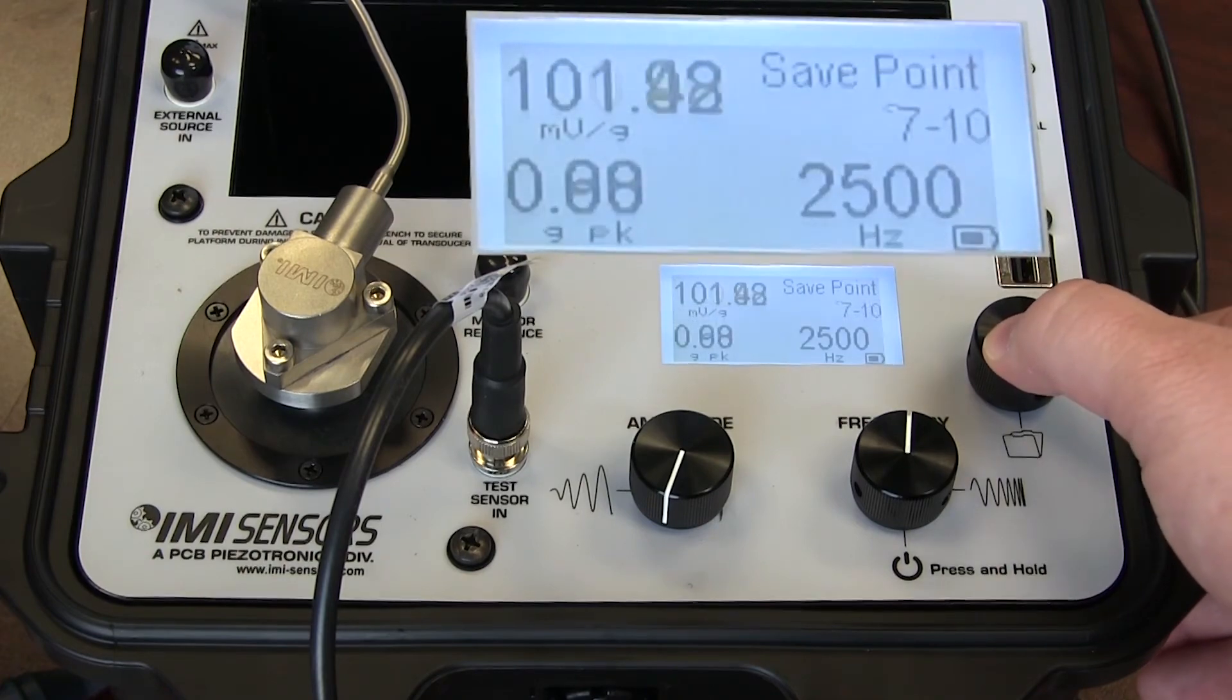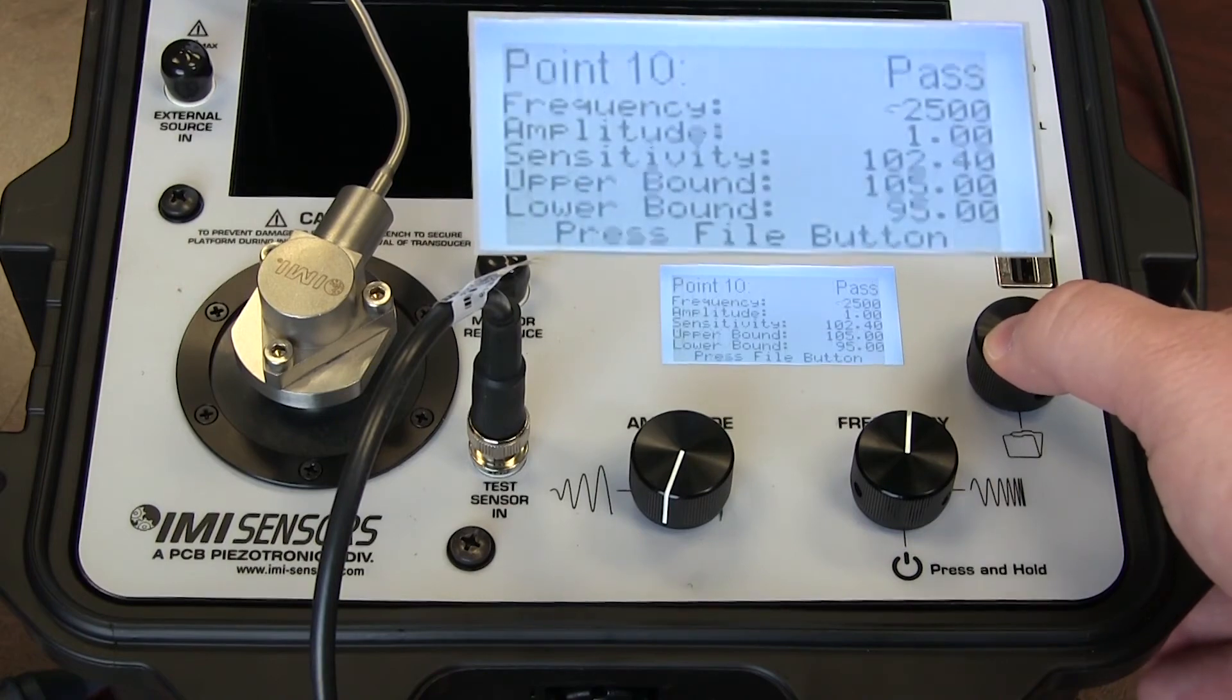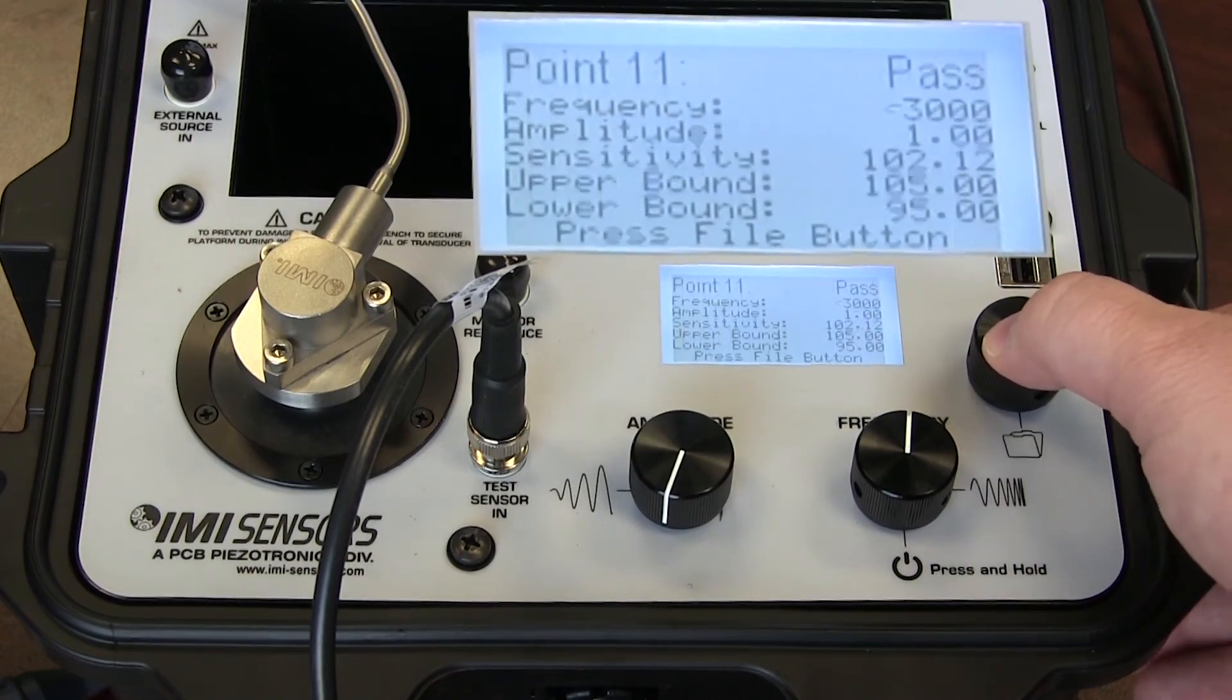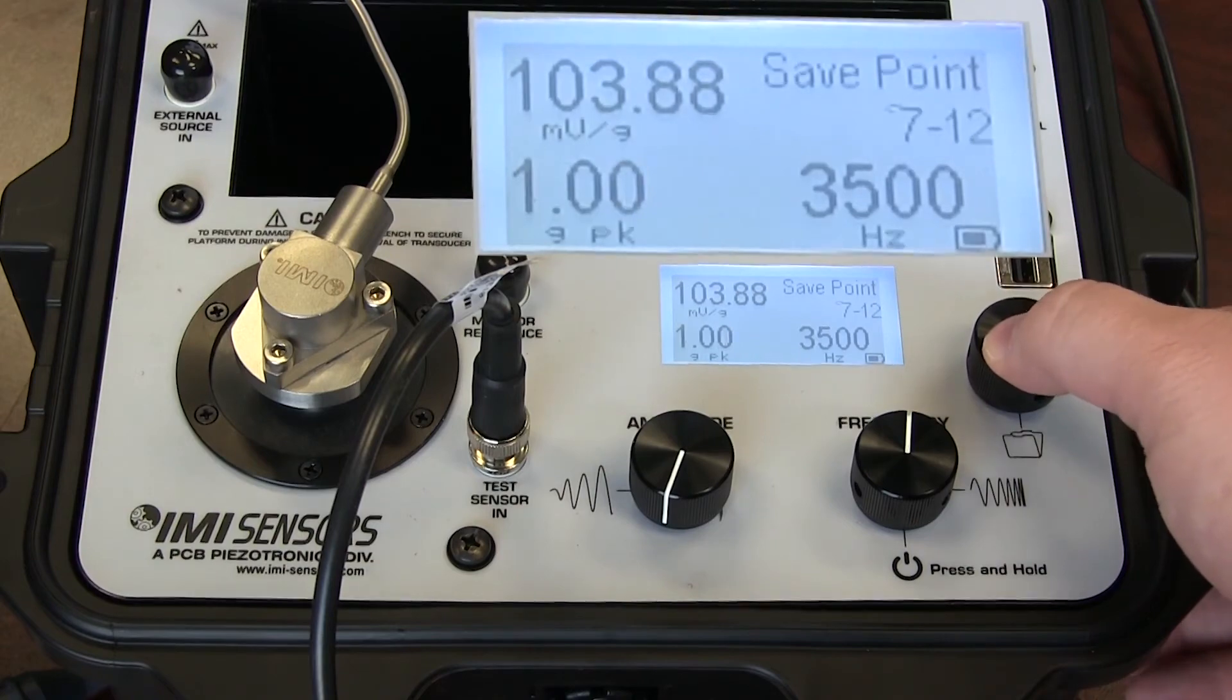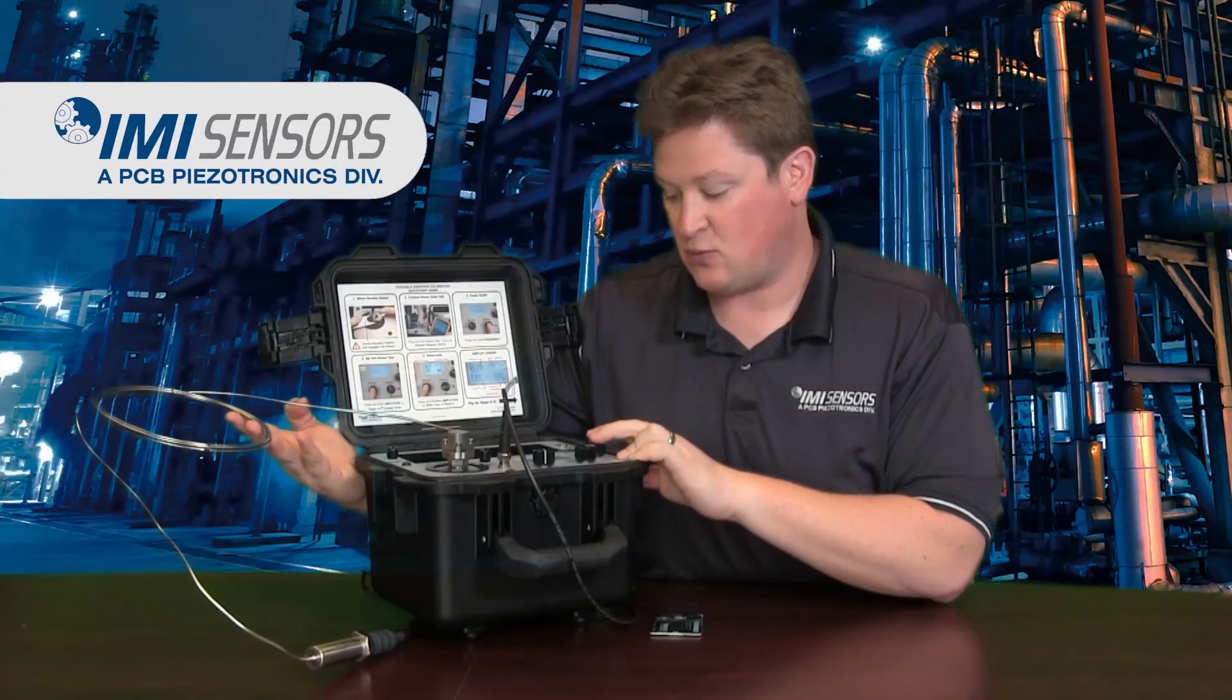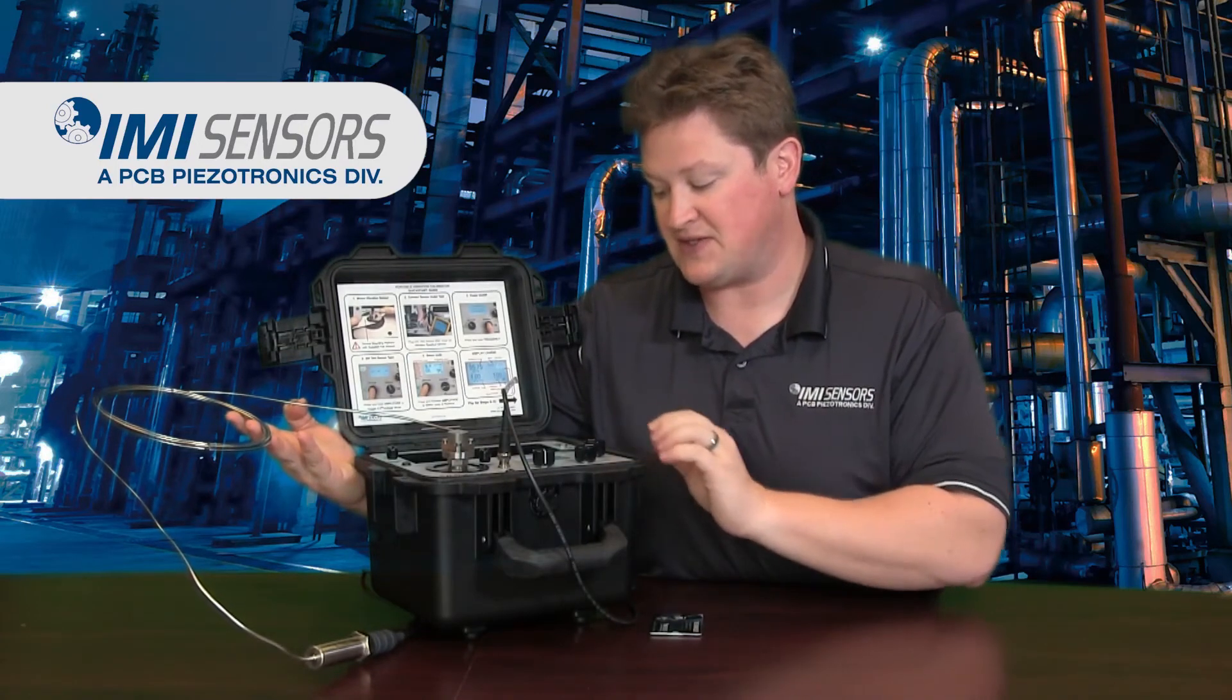At 2000 Hz, we pass. At 2500 Hz, we pass. And there's only two test points to go. 3000 Hz, pass. And 3500 Hz, we pass again. It'll tell me when I hit the button. 3500 Hz, we pass at 104 mV per G as we start to approach the sensor's resonance here.